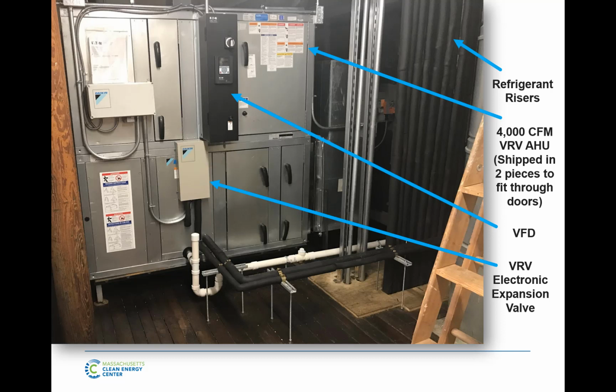So now what you're looking at here, that's a 12-ton VRF air handler. So it's a 2-piece air handler, so we could fit through doors like a regular semi-custom air handler. Fit through doors, we stacked one, stacked the other. This is your VRV expansion valve, like I talked about in the fan coils, but it's a loose one that we can install. Your expansion valve controller, that's a VFD for the supply fan that sits back there. Down here are your refrigerant lines up to the roof, and these are all the other refrigerant lines because there's 6 mechanical rooms on top of each other, each with 3 of these machines.